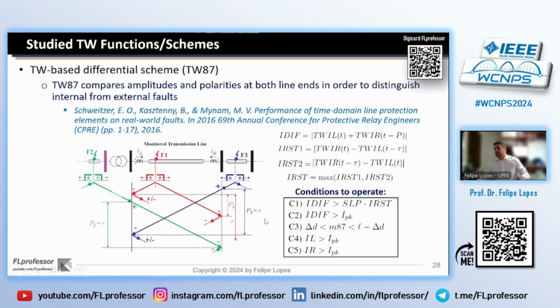The traveling wave-based differential scheme compares the polarities and amplitudes of traveling waves at both line ends. You can find further details in this paper. Basically, for internal faults, the first traveling waves that reach the transmission line terminals will be separated by a time period which is shorter than the line travel time. But for external faults, they will be separated exactly by the line travel time.